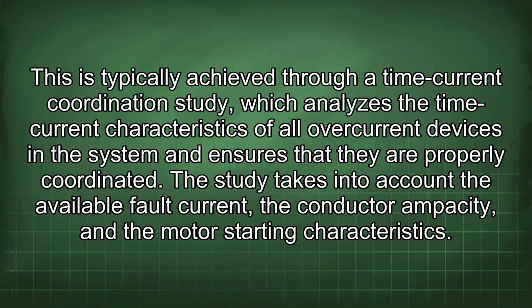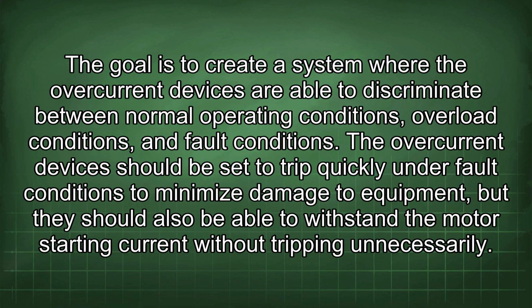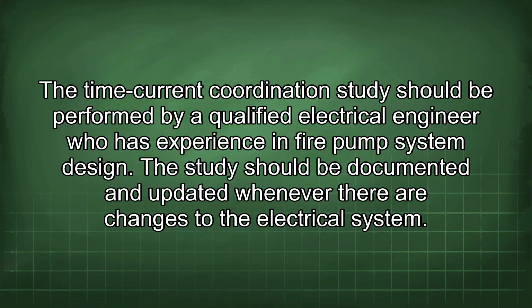The study takes into account the available fault current, the conductor ampacity, and the motor starting characteristics. The goal is to create a system where the overcurrent devices are able to discriminate between normal operating conditions, overload conditions, and fault conditions. The overcurrent devices should be set to trip quickly under fault conditions to minimize damage to equipment, but they should also be able to withstand the motor starting current without tripping unnecessarily. The time current coordination study should be performed by a qualified electrical engineer who has experience in fire pump system design. The study should be documented and updated whenever there are changes to the electrical system.